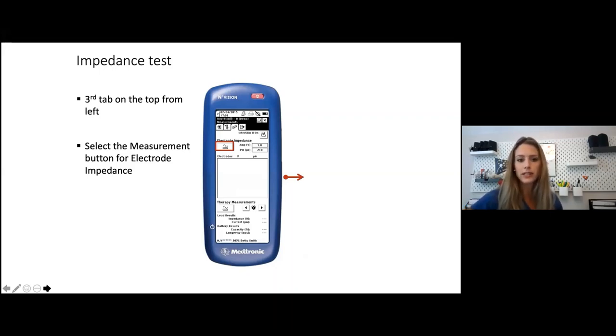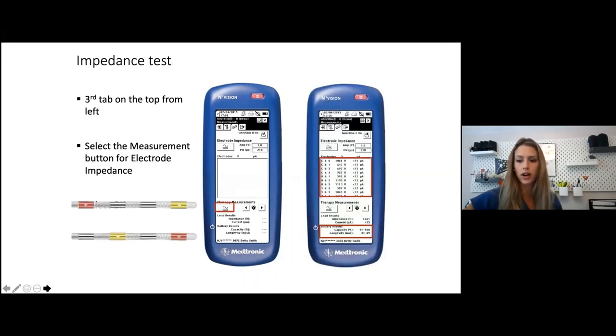Impedance is measuring the resistance, which is part of Ohm's law as well. So when you're measuring this impedance, it'll pre-populate the amplitude and pulse width and actually give you a measurement in ohms of the resistance between each electrode combination. When you press the impedance test button, in about a minute you'll have a reading of all the connections and what the impedance reading is.